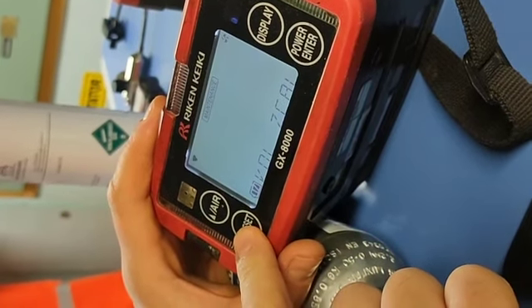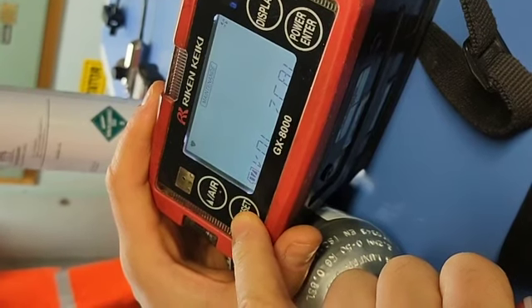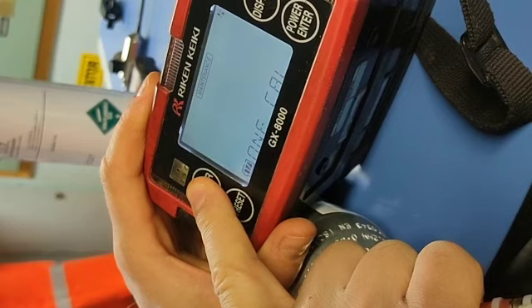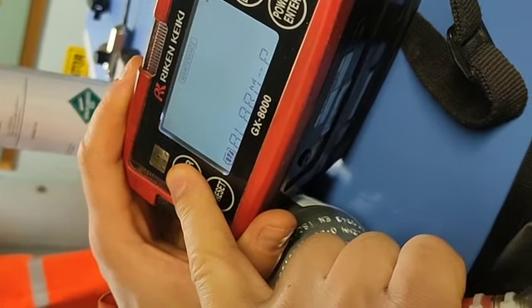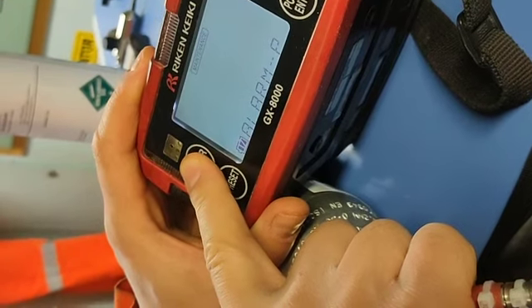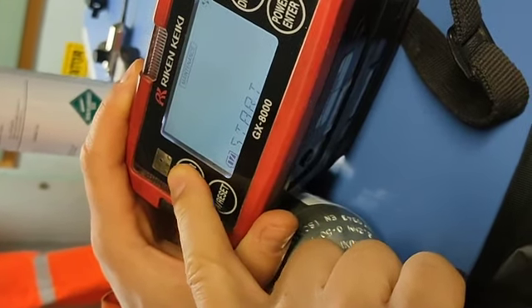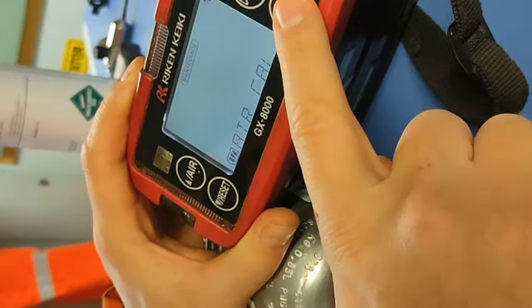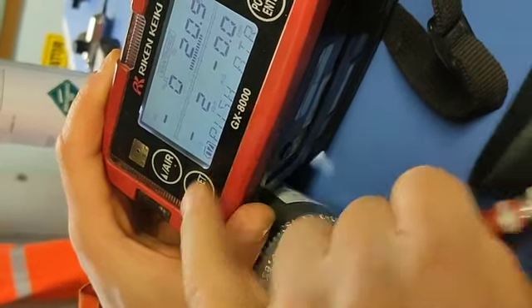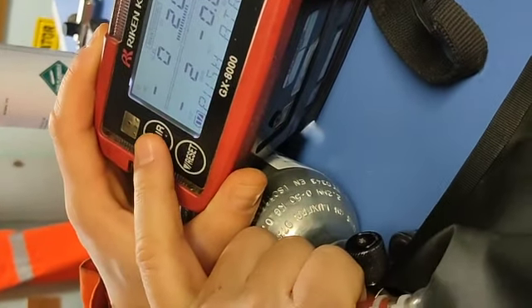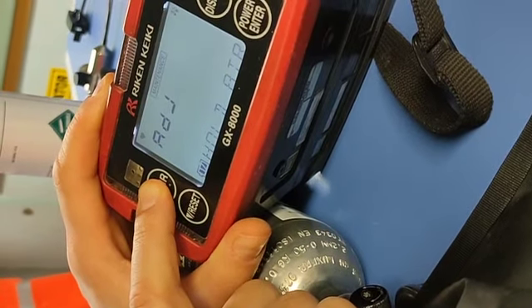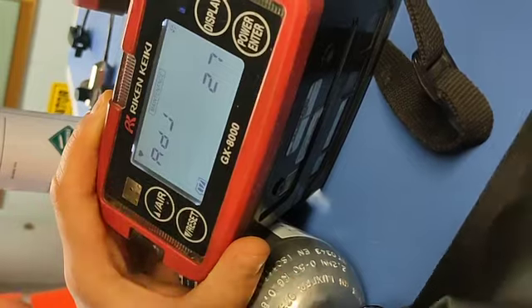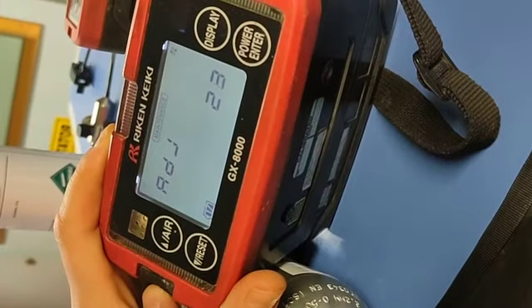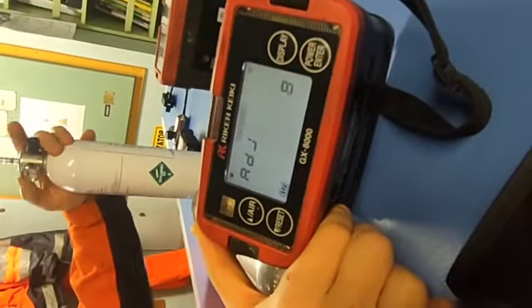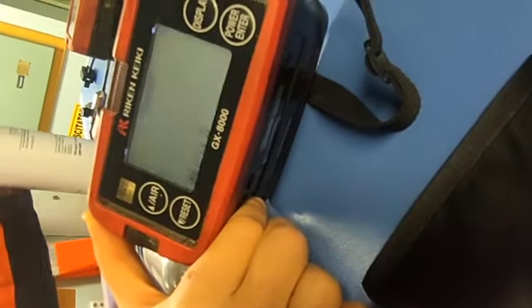Now, to be able to go to the next step of the calibration, we have to make air calibration to bring the oxygen sensor to 20.9 and all the other sensors to zero. So we go to air calibration in the same menu. If we press one time, it says push air. Push air means push the air button. Hold air, we will hold the air button, and release, we will release it. Okay, we are good to go.